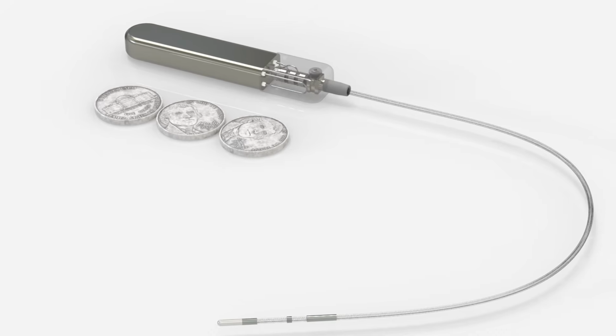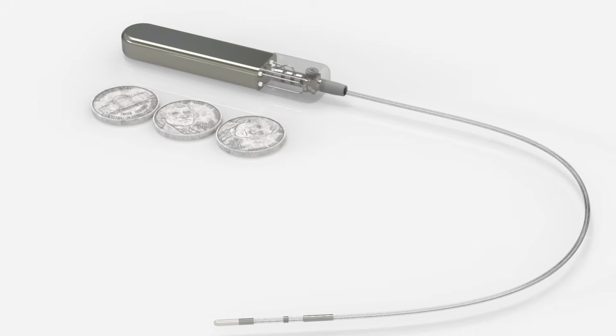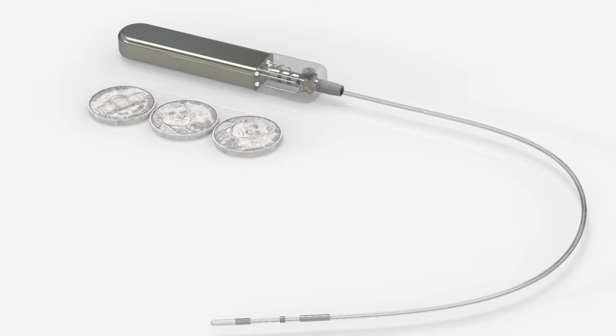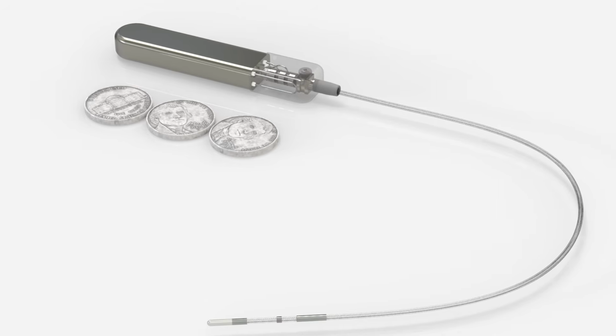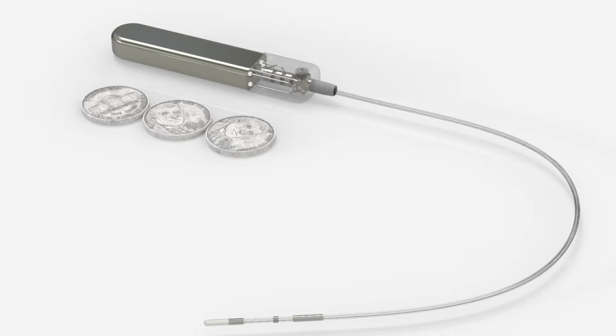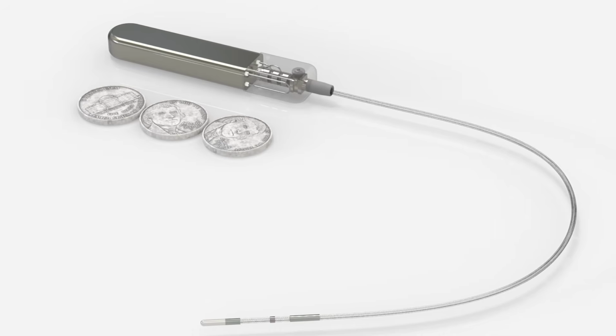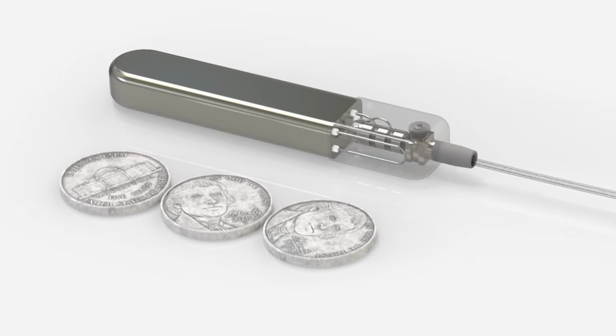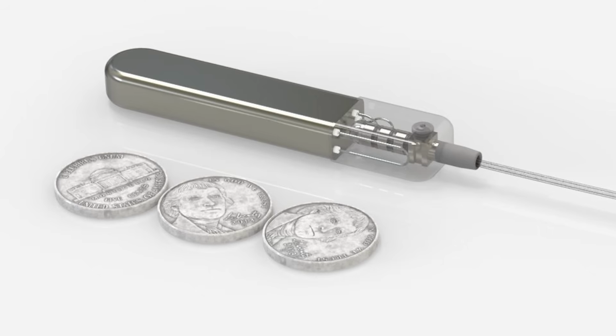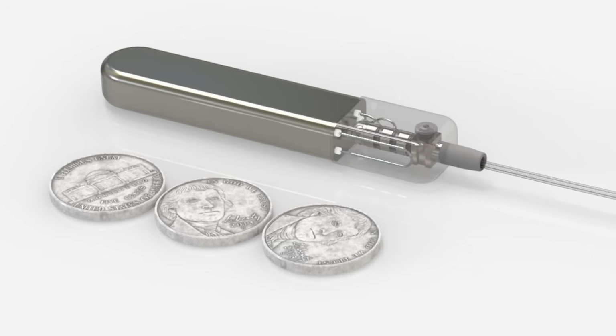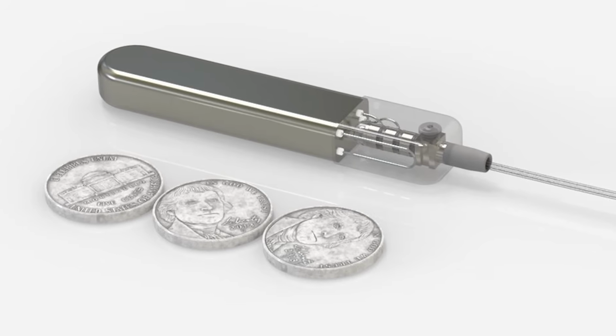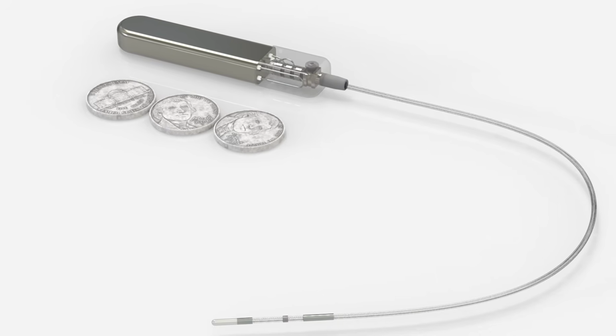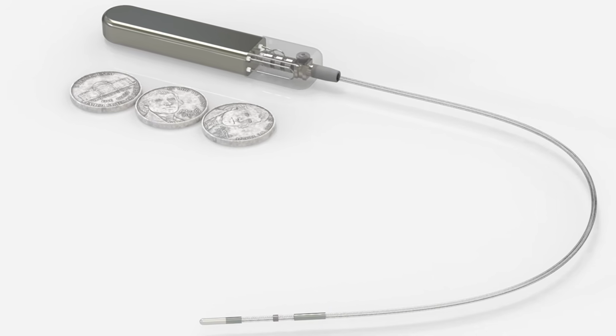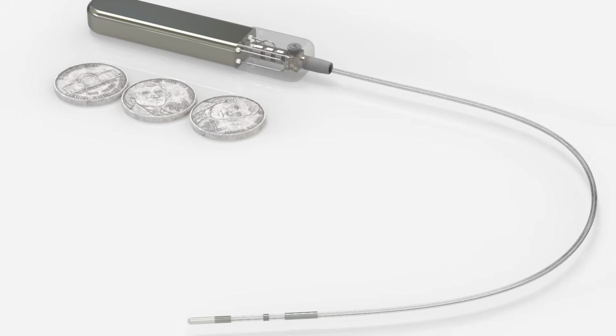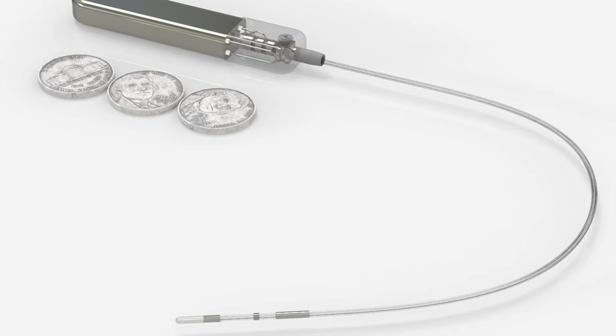Explain to us what Glucotrack looks like. Okay, so the electronics, the device, is housed in a titanium housing, designed just like an implantable loop recorder. It's actually using a battery from an existing commercial implantable loop recorder for cardiac monitoring. About 2/3 of the length of that device is battery, to give us our 3-year longevity. Out of the remaining 1/3, half is electronics, and the other half, the clear plastic part at one side of the device, is where we connect the lead. If you think of the G6 as an example, you had a sensor carrier and a plug-in electronics transmitter. It's kind of like that, right?